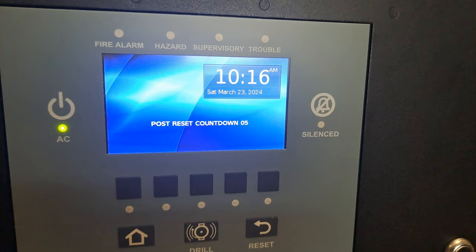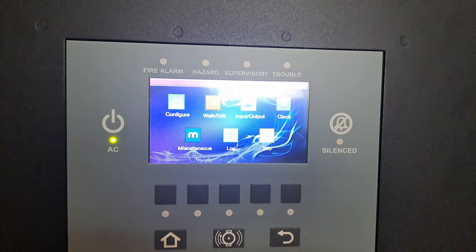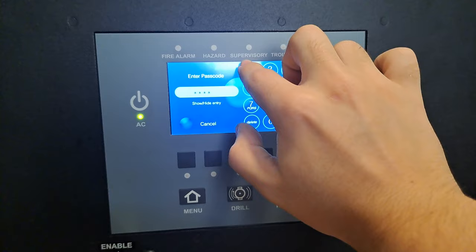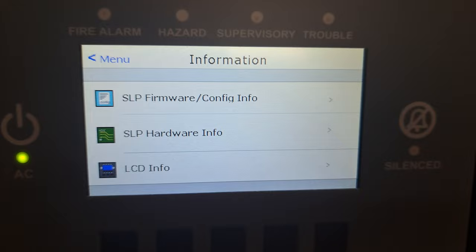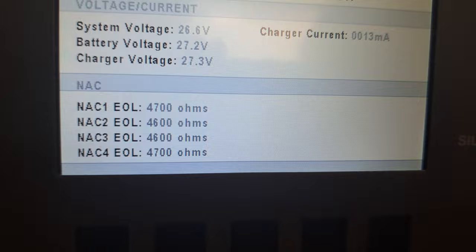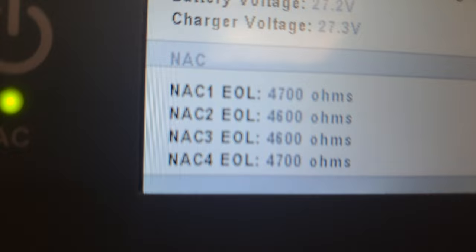I'm gonna show you this neat feature they have. Level one password is all ones, by the way. You click on SLP hardware info and it shows you all the voltage and even the NAC resistance. It uses 4.7k resistors, and as you can see, they're all basically 4.7k except the middle two.